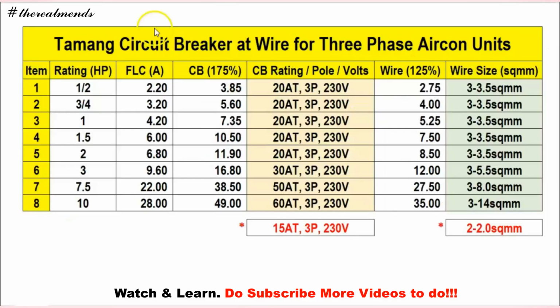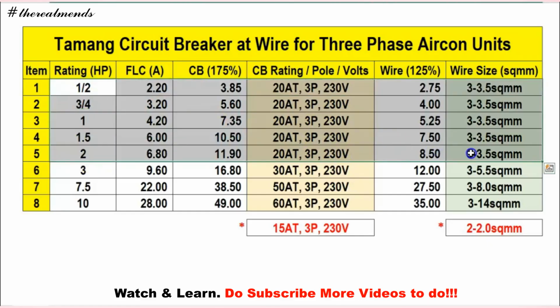Okay, to continue, so from the table, meron na tayong wire size, yung column niya, and then yung selected na wire, meron na tayong schedule ng wire. So, for 1/2 HP, meron tayong 3.5 square mm. So, tatlong line. Line 1, line 2, line 3. So, the same ng circuit breaker until 2 HP. So, means to say, the same din yung kanilang wires, 3.5 square mm. Up to 1/2 up to 2 HP.